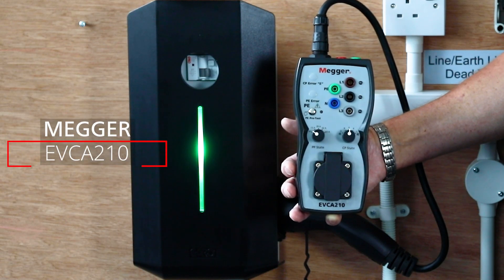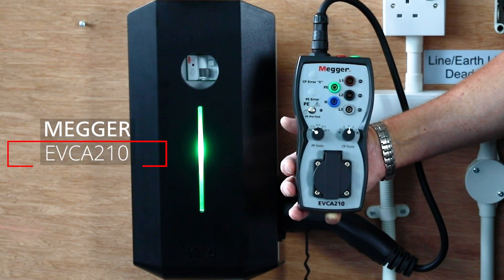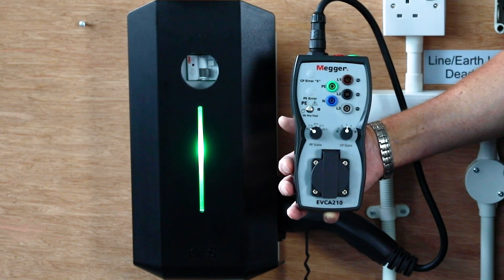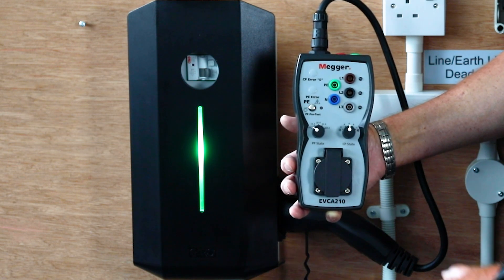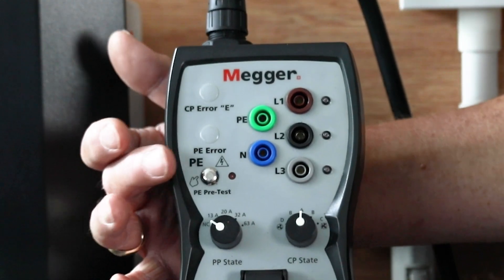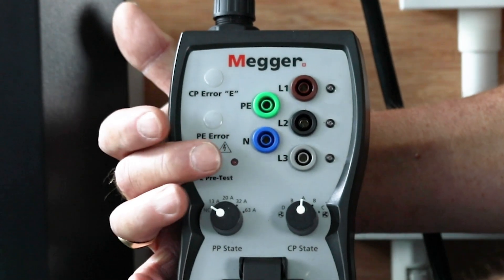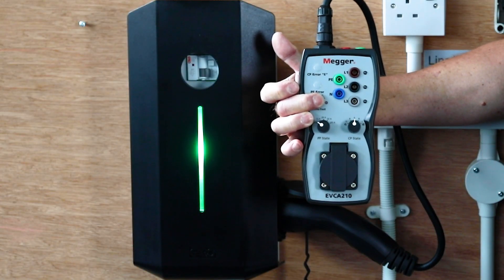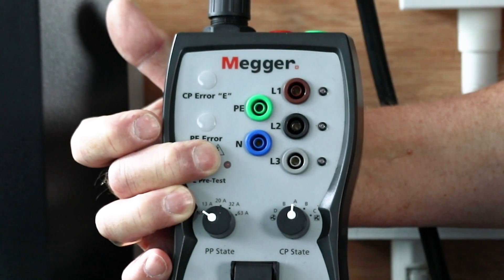We're looking at the Megger EVCA210 electric vehicle charging adapter and we start by looking at the pre-tests that you can actually do on the tester. The most important of which is the PE pre-test. This is a simple discharge point for touch voltage to make sure that there's no potential on the earth of the vehicle. You must check this at every selection on the tester.